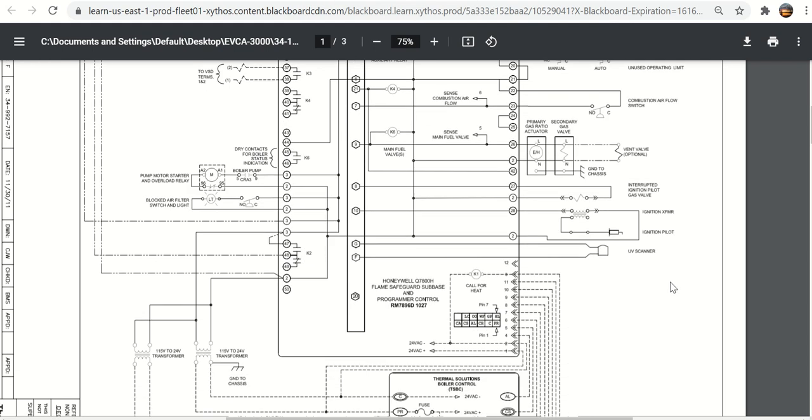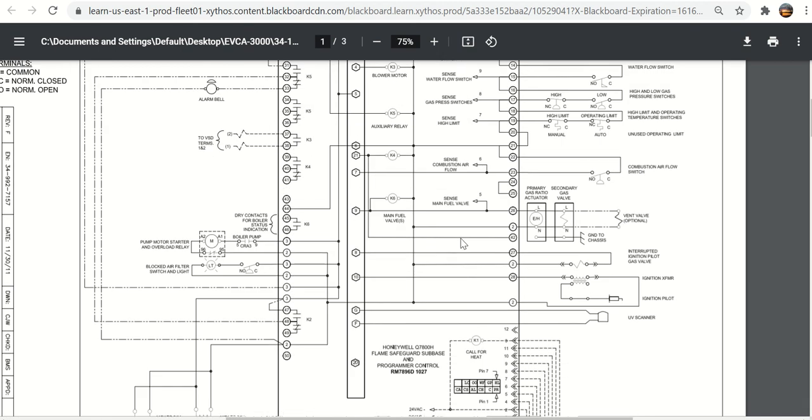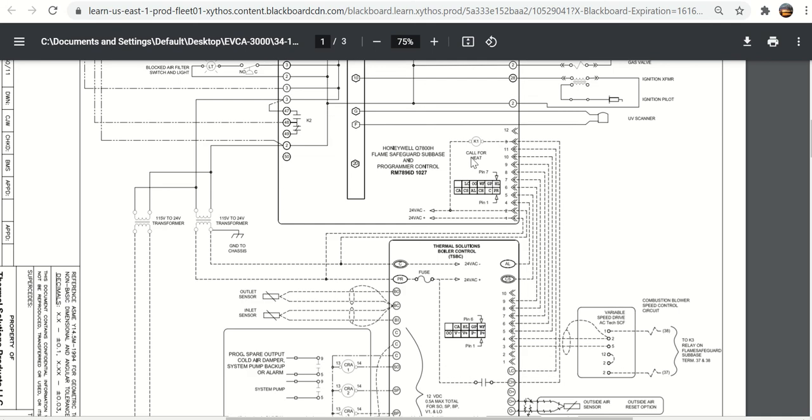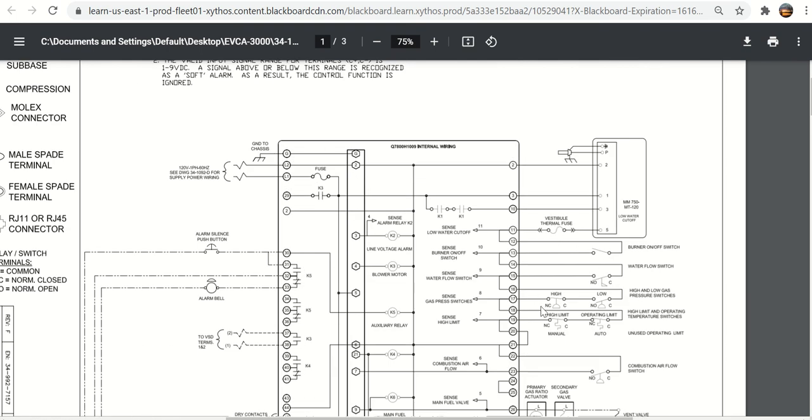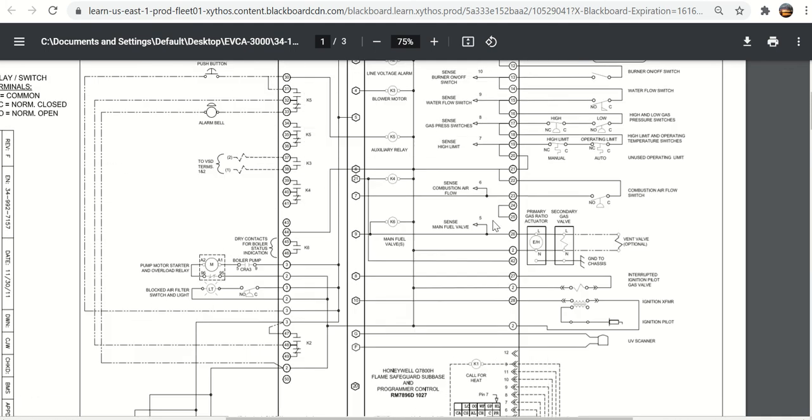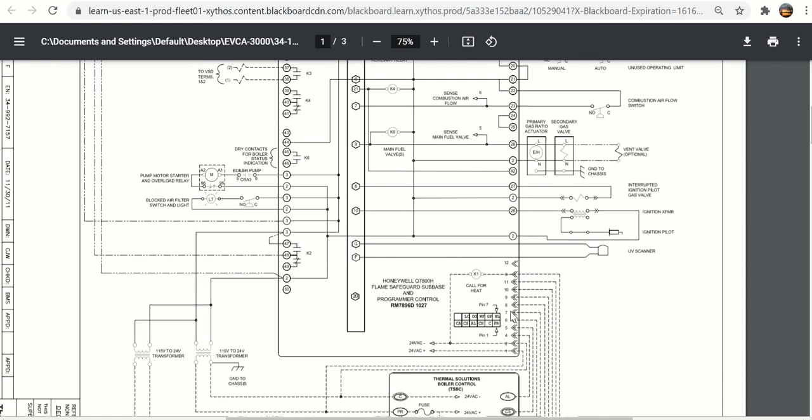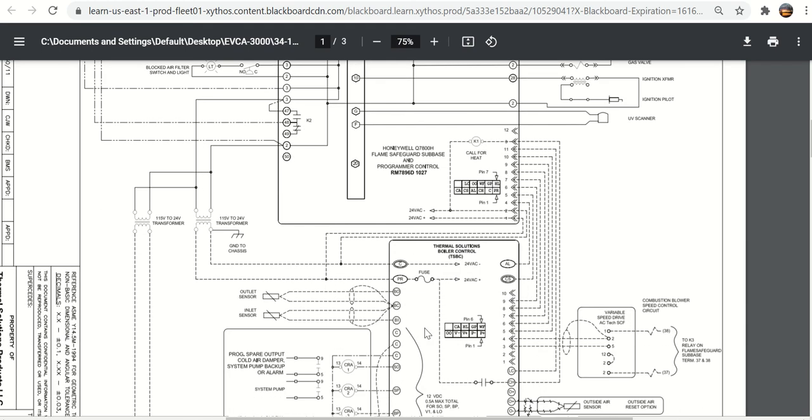The thing that is neat about this is you see here where it says low water, burner on off, water flow, gas pressure, high limit, combustion air, main fuel valve. All of those go to terminals here. They've got initials here that show those terminals. Those terminals, through a ribbon cable, go down to the TSBC boiler control. That's how the flame safeguard and the information that comes from these safety controls can be enunciated on the two line display of the thermal solutions boiler control. It can monitor whether the low water cutoff is made, the burner switches on or off by power on these terminals with a ribbon cable coming down to the thermal solutions display.